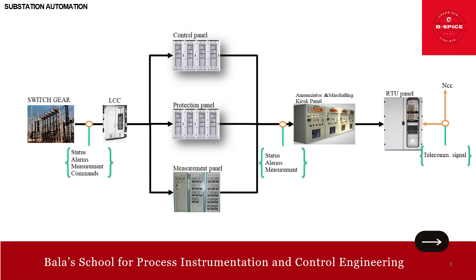The signals from the LCC go in parallel to the control panel, protection panel, and measurement panel. The control panel is responsible for switching, monitoring, automation, and annunciation. Switching means it manages the operation of circuit breakers, transformers, and other equipment. Monitoring provides real-time data on the status of various substation components. Automation implements automated processes to enhance operational efficiency, and annunciation alerts operators to abnormal conditions or faults.